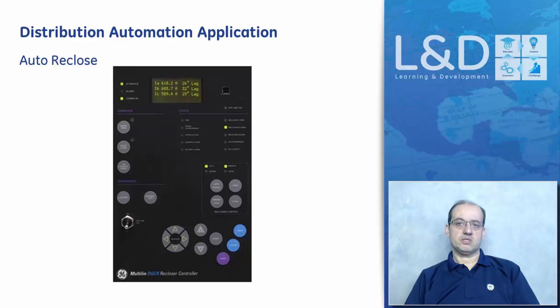Each automatic reclose function can support multiple trigger status inputs to indicate the protection has operated and the automatic reclose function should be initiated. The dead time is the time between the detection of the circuit breaker trip and the automatic reclosing of the circuit breaker. The reclaim time is the time following the circuit breaker being reclosed, during which time a further opening is considered to be part of the current reclose operation.